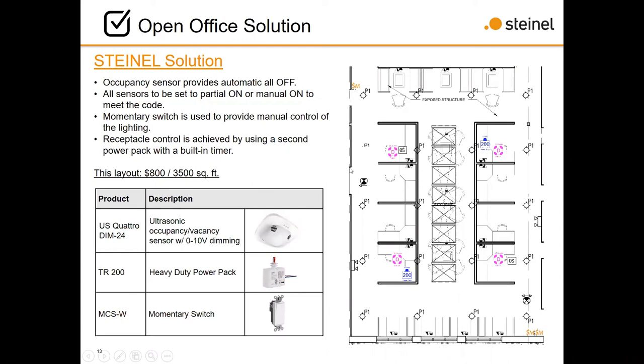4 ultrasonic DIM 24s, and some of the capabilities we're looking to provide here: because we've got the DIM 24 with the photo sensor on board, you do have the ability to do daylighting in any daylighting zones. We're using the TR200 power pack to power those, and you can see we've got 2 power packs powering the 4 sensors. And then we've got a momentary contact switch at each of the doorways, right? So we're providing automatic off. We're providing partial on with the dimming control.